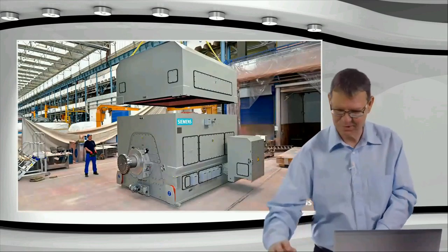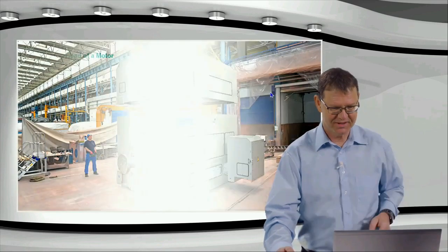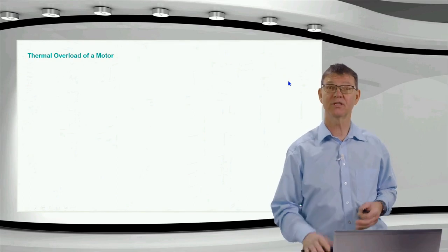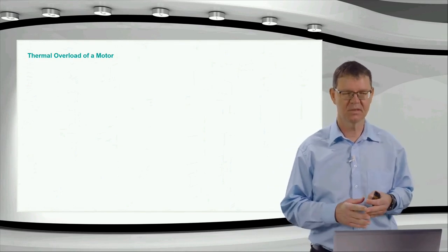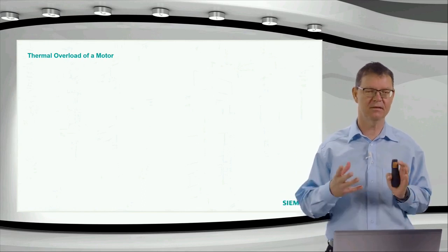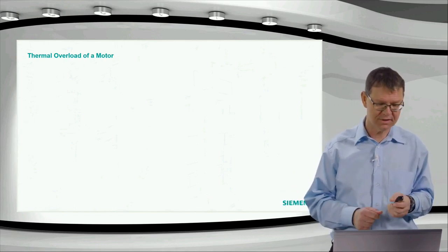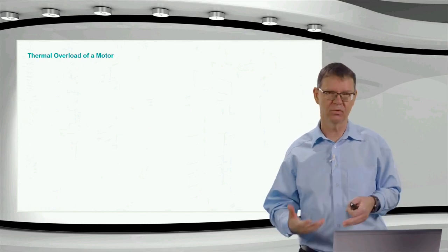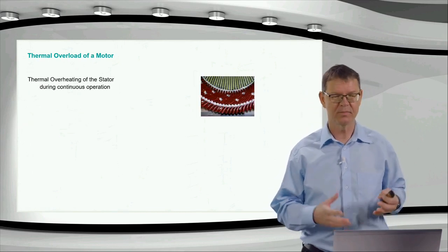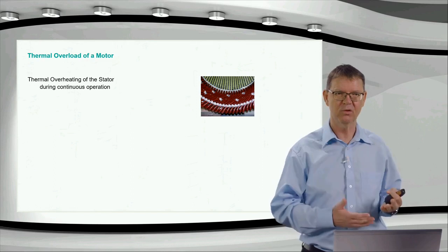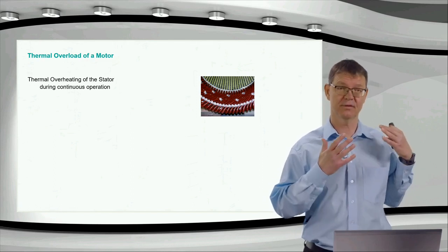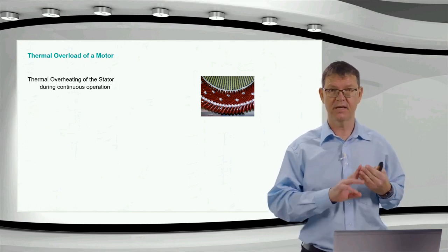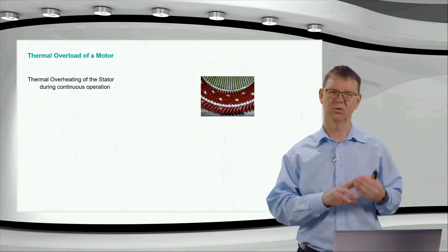Yeah, let's attack the last part here about the thermal protection, the overload protection of a motor. I spent some extra slides to explain the theoretical background, and then we go for the settings. So basically, where do we have thermal overload protection of the motor? On the one hand, I have the protection of the stator. The stator gets stressed normally during normal operation.